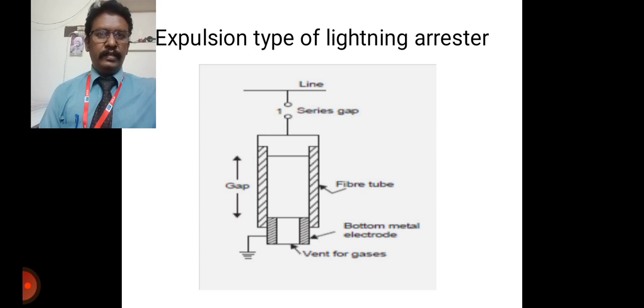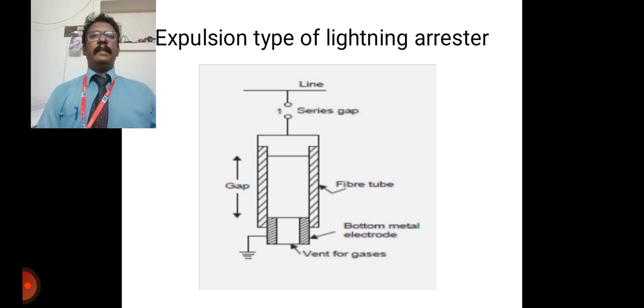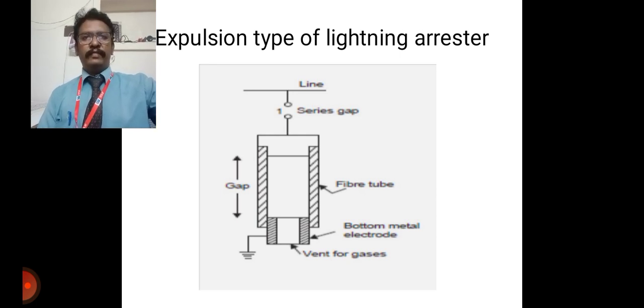You can see the diagram. Here we have a line, we have a series gap, then we have a lengthened gap with fiber tubes. At the bottom, you can see here, bottom metal electrodes. Finally, you have a vent for gases. So you can see in the diagrams. So with this only, we are going to elaborate how the expulsion type of lightning arrester is going to function.